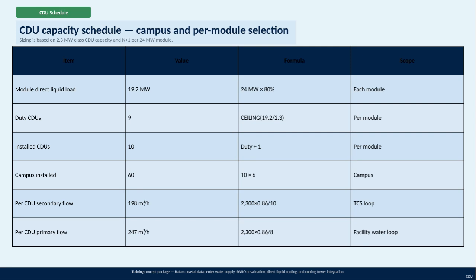However, to maintain N+1 redundancy, we install 10 CDUs per module. Since the campus includes 6 such modules, the total number of installed CDUs is 60. Regarding flow rates, each CDU handles a secondary flow of approximately 198 cubic meters per hour within the thermal cooling system loop, and a primary flow of about 247 cubic meters per hour in the facility's water loop.